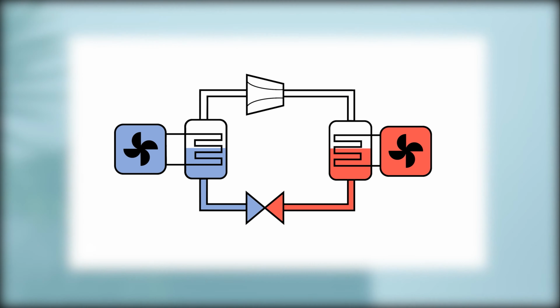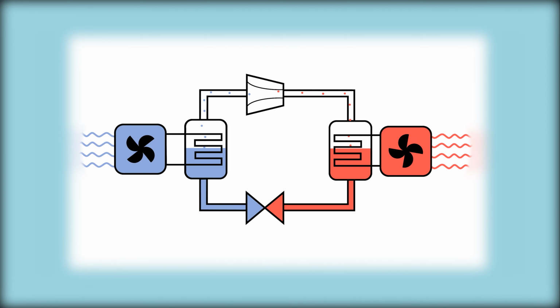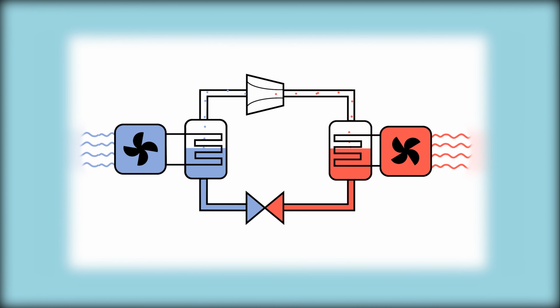In the evaporator, the liquid refrigerant gets vaporized by the heat of the items being refrigerated. This gas travels along to the compressor, where the pressure and temperature is raised. The hot gas then gives up its heat in the condenser, where the heat is released to the surroundings. The hot gas then travels back to the expansion valve and returns to cool liquid. This liquid travels back to the evaporator, allowing the cycle to repeat.